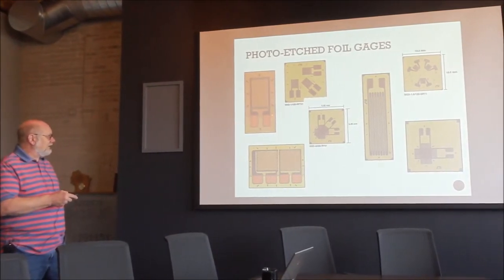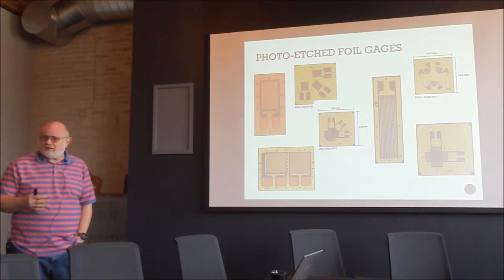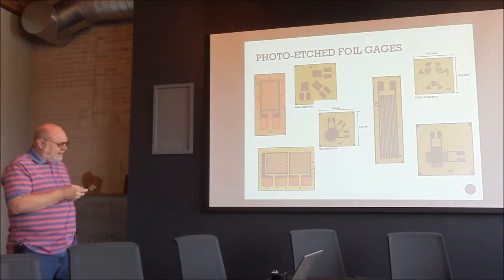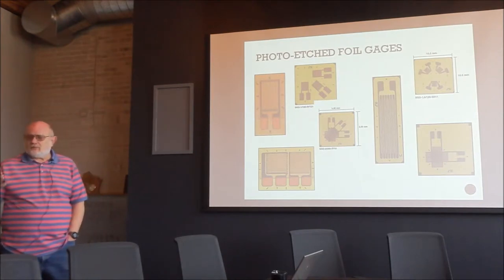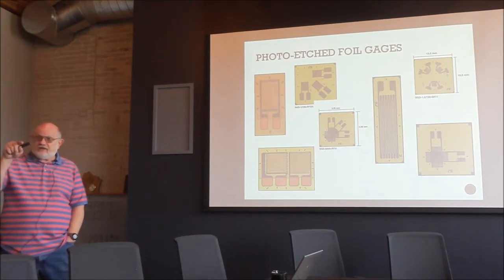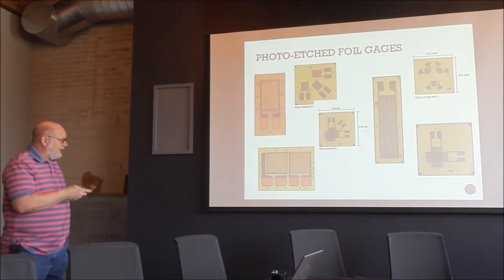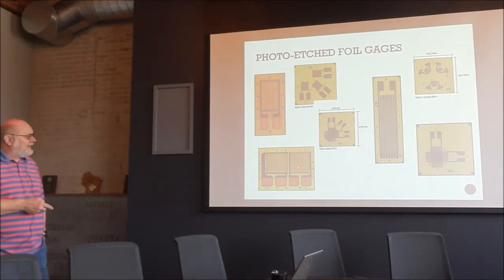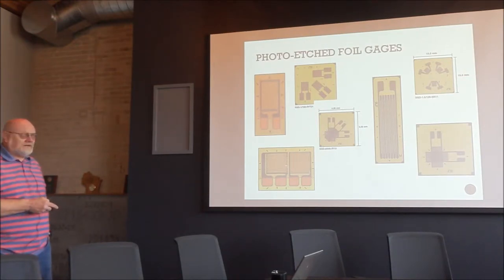A standard foil gauge — here a CEA gauge — has a polyimide backing with a Constantan element, which has a low thermal coefficient of resistivity. The alloy is adjusted to match the substrate's CTE: a zero designation for pyrex/borosilicate, six for steel (6 ppm), thirteen for aluminum (13 ppm). A biaxial gauge with a transverse element negates Poisson's effect for precision instruments.